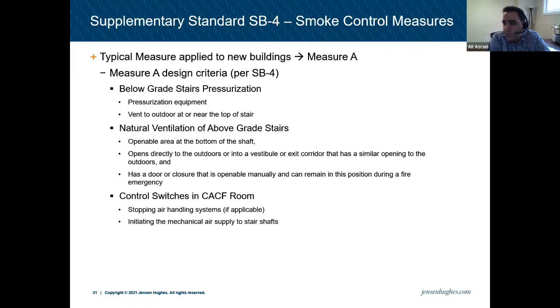So the typical measures that I said are applicable to buildings: measure A is very common for new buildings. The design criteria is per supplementary standard SB4. It's asking for below grade stairs to be pressurized. So you have pressurization equipment for the below grade, and there's a vent to outdoors at or near the top of the stair. So you put the fan at the bottom of the stair and a kind of louver and exhaust or whatever at the top of the stair.